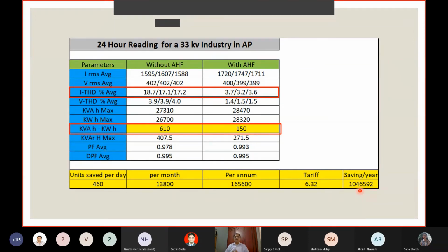Now this is not 10 lakhs, the investment was close to 60 lakhs for all the filters and facility and the air conditioning that was created for the 300 ampere filter, active harmonic filters and all that. But then the fact is, after this has been done, it is almost, if I am not mistaken, almost 5 years since we did it. The PCB failure has come down to virtually zero.